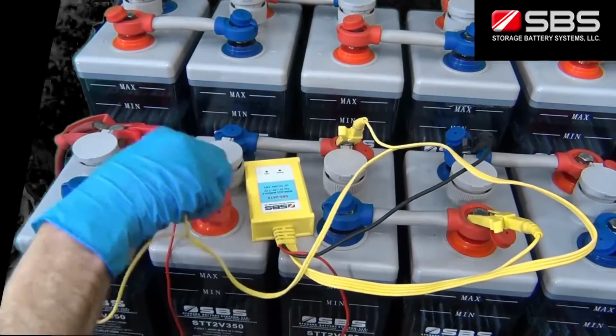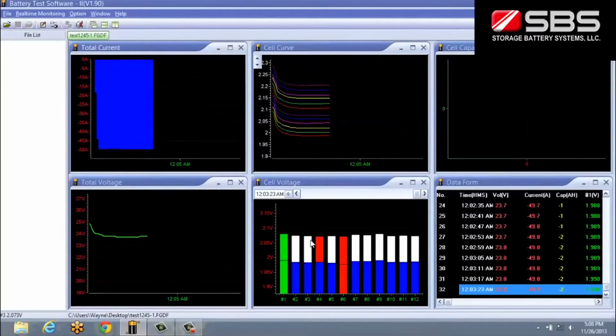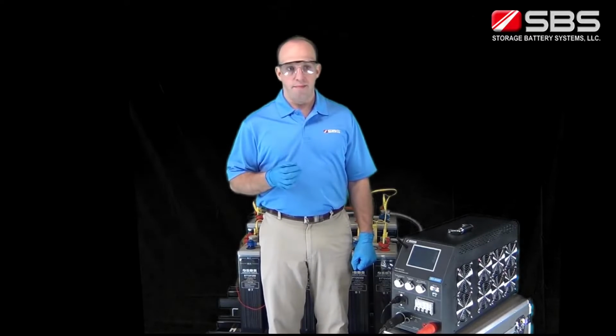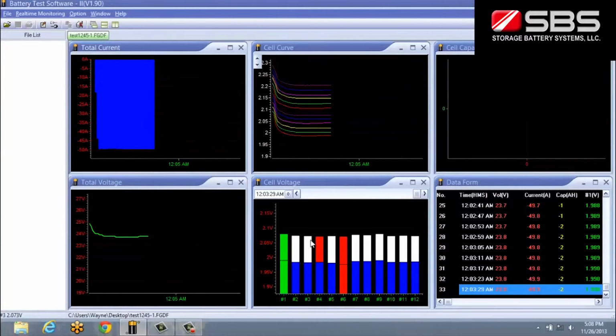feet of test wires. It comes with an advanced analysis software program that allows for real-time communications, data capture, and display on a PC during testing. The SBS-8400 also stores all of the data internally for downloading to USB memory device for manual transfer to a PC at a later time. The software is also capable of generating detailed graphic reports for reviewing or printing.